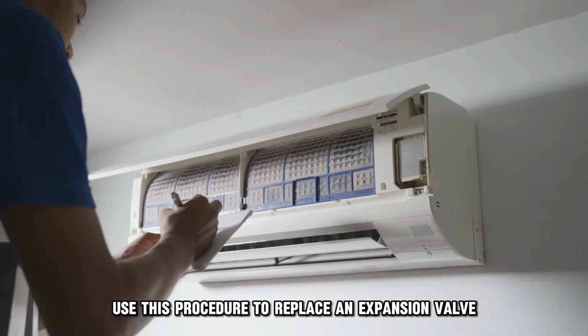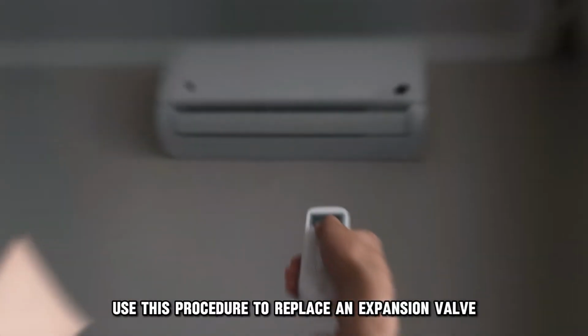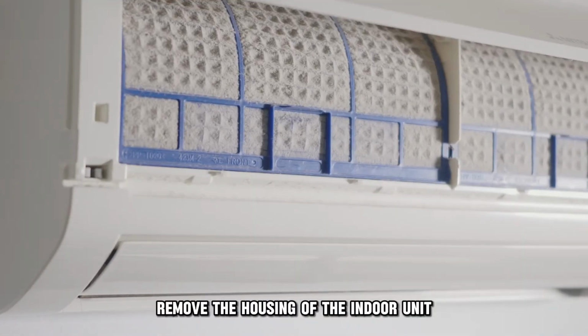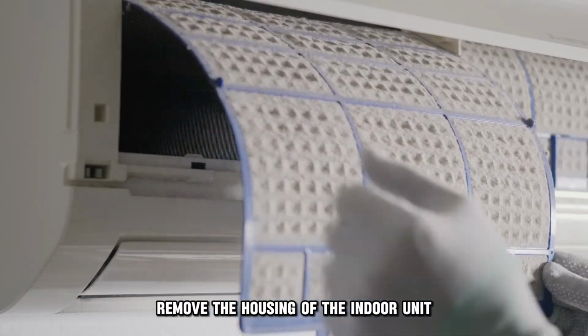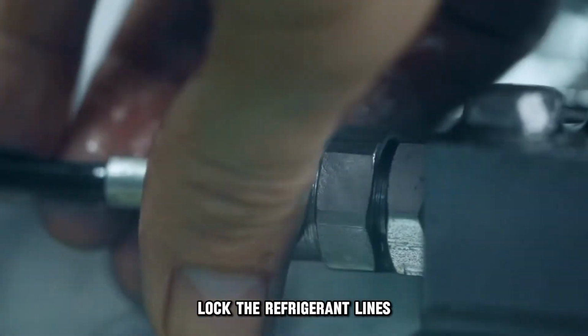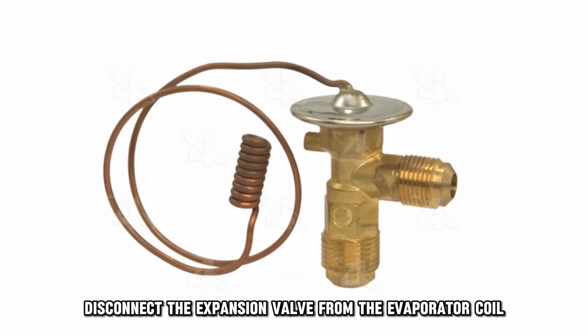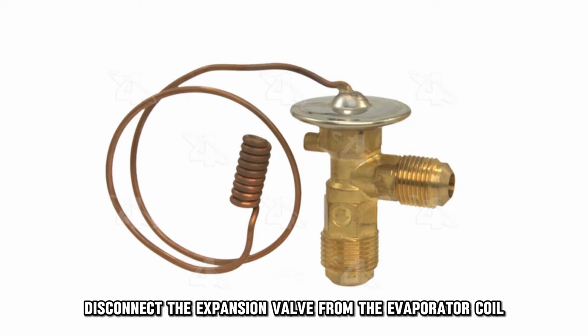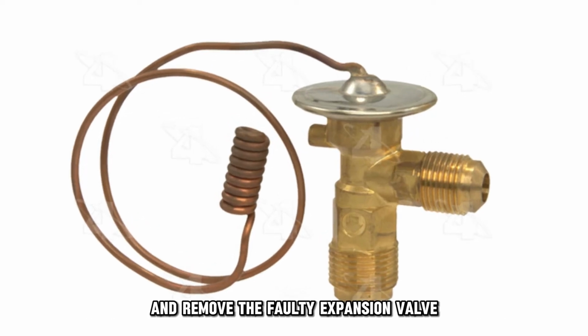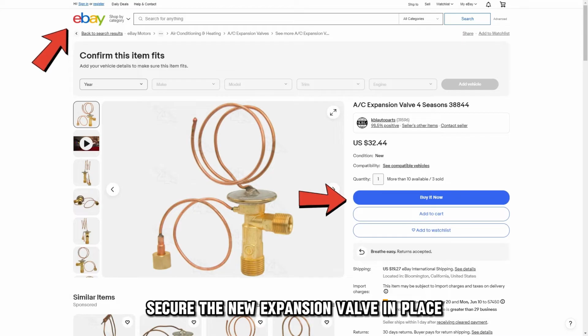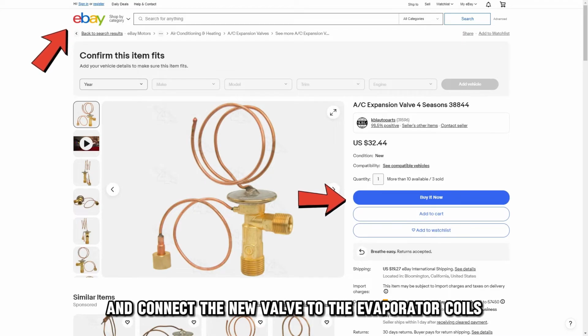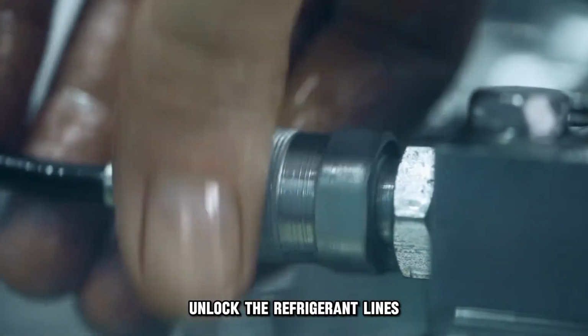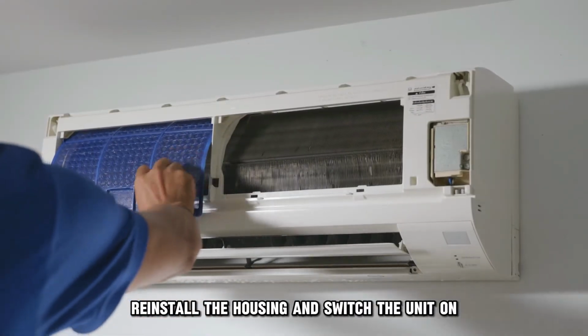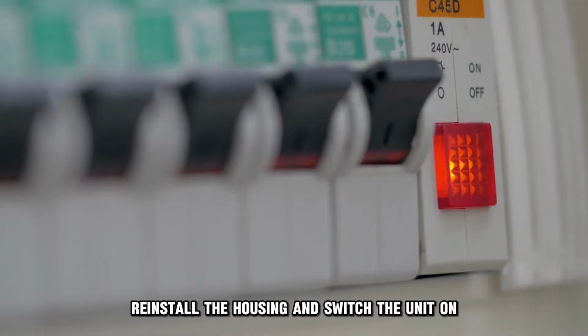Check the expansion valve. Use this procedure to replace an expansion valve. Switch the unit off, remove the housing of the indoor unit. Lock the refrigerant lines, disconnect the expansion valve from the evaporator coil, and remove the faulty expansion valve. Secure the new expansion valve in place and connect the new valve to the evaporator coils. Unlock the refrigerant lines, reinstall the housing, and switch the unit on.